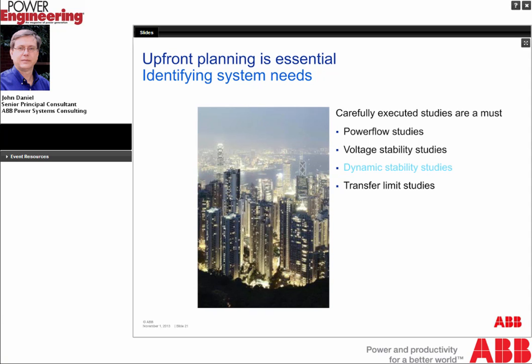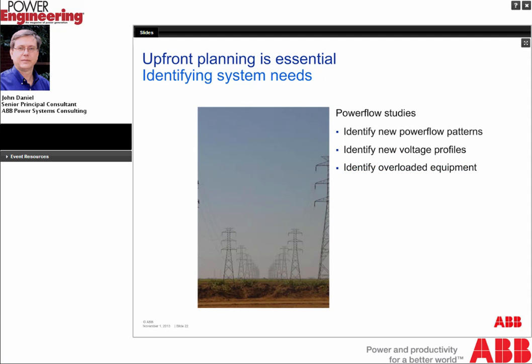So with all of this, upfront planning becomes very essential, and it's important to carefully study the issues. These studies can include such things as power flow evaluations, voltage stability studies, dynamic stability studies, and even an evaluation of the transfer limits across the system. The benefit of the power flow studies is that it helps to identify the new power flow patterns and voltage profiles across the grid so that you can understand where support may be needed and how you might be able to provide that support.